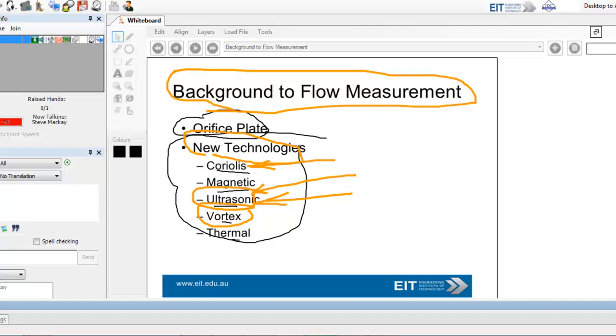Vortices, medium to high accuracy, medium cost, excels at measuring steam, very versatile, liquid, gas, steam, you name it. No worries at all. And then the other disadvantages probably are, it's a body in the middle of a stream of liquid, so it could be knocked out of position. Vibration can impact on the accuracy. It's not as widely accepted, so you don't get industry approvals across, and high accuracy is a little bit missing.